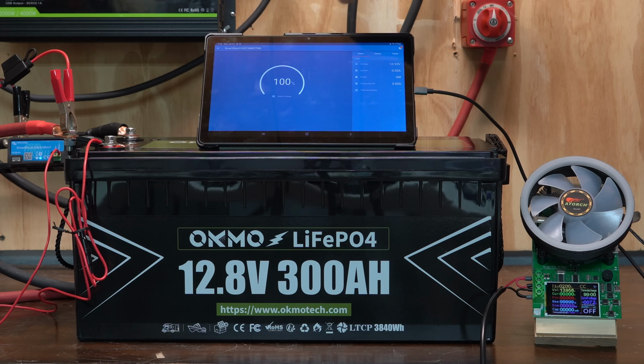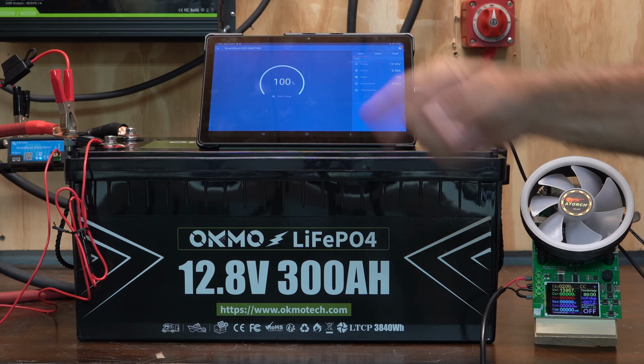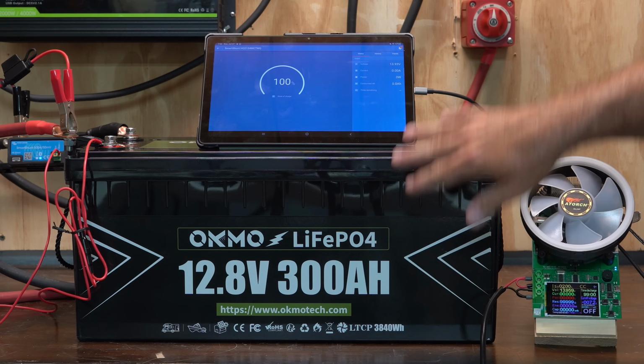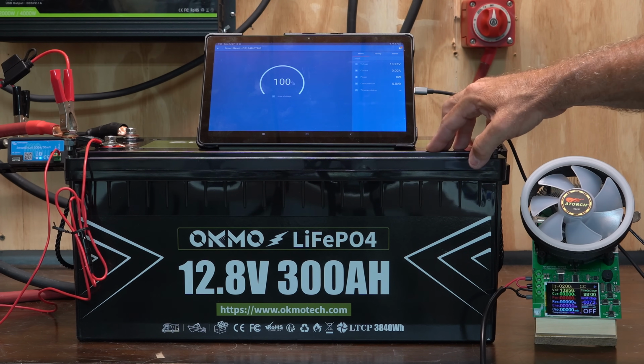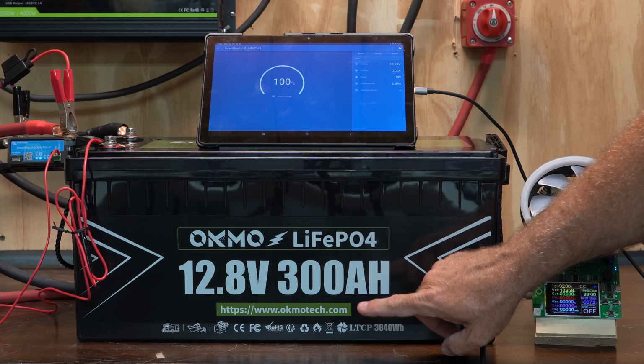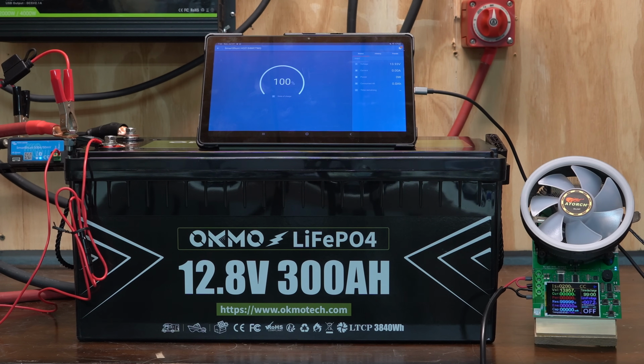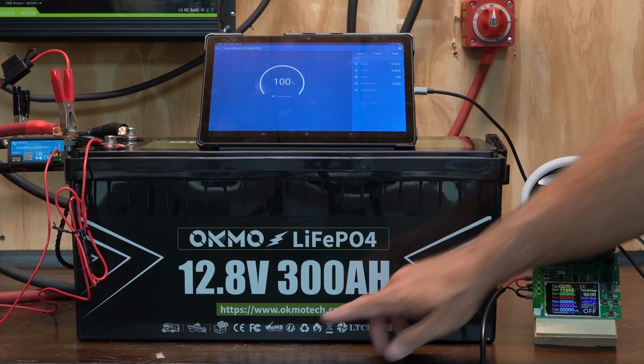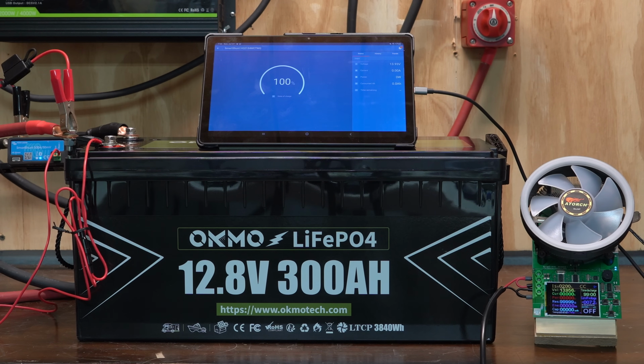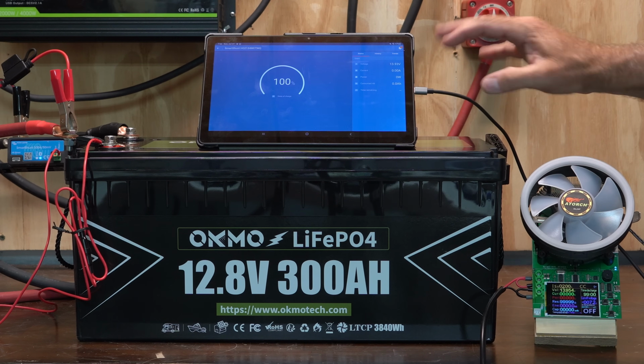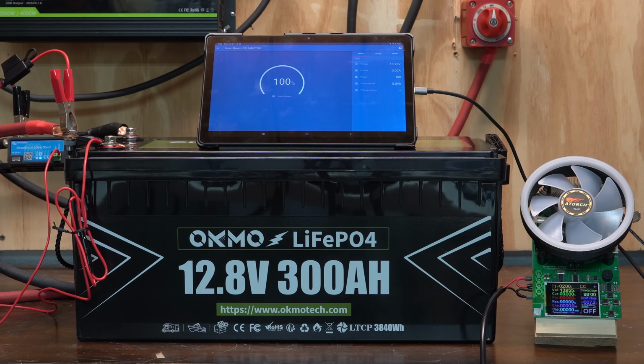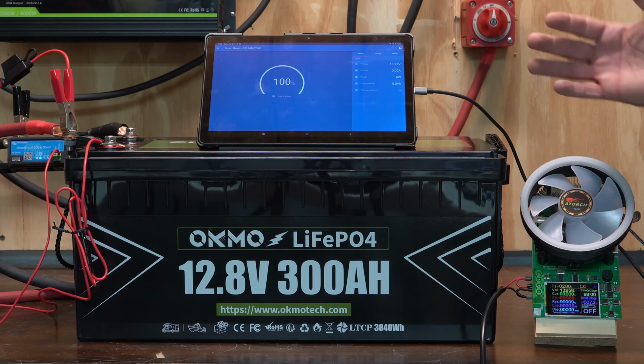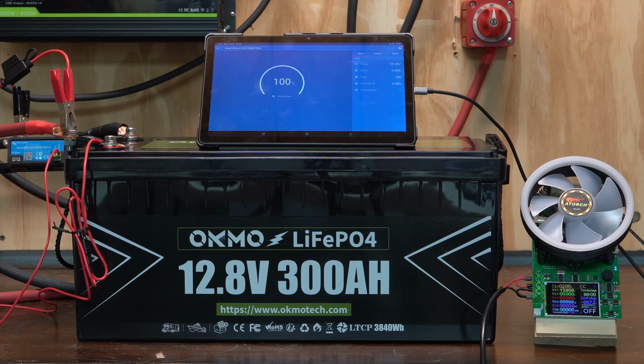I've also got these feeding into a 2000 watt inverter, connected to a couple of variable charge power stations. We want to discharge this using an industry standard 0.2C discharge rate. So 0.2C times 300 amp hours gives 60 amps, and 60 amps times 12.8 volts gives a discharge rate of about 768 watts. The reason I have my battery tester here is that my inverter will actually shut off due to low voltage disconnect before the BMS cuts off, so once the inverter shuts off, I want this thing to finish it out. At the very end we won't be discharging at 0.2C anymore, but that's okay, I just want to get it close.